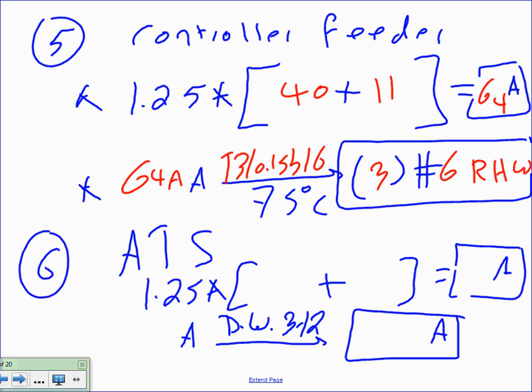ATS, sizing the ATS. When we size the ATS, guys, we do the same thing. This is opinion. Everything I say is opinion. The ATS is my opinion. And believe it or not, my opinion should count, right? 64. At least for the class. So 64 amps, then you take the 64 amps that you got, up there, to D.W. 3-12, Chris, still 3-12 from a year ago. And when you have that, what's your next ATS? 100, right?